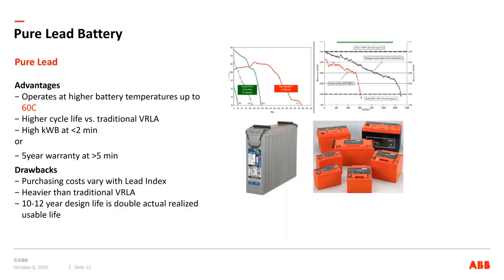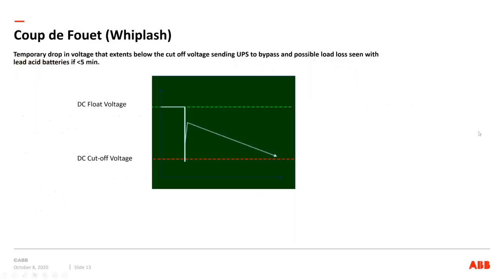The one benefit, and it'll tie into, actually we might as well go to the next slide, slide 13, with a fancy French word, coup de fouet, which is something that some data centers, some facility managers have learned the hard way. In a lead acid battery, it is chemistry. So when the UPS suddenly needs power, it's a load step on the battery, and the chemistry needs to wake up before the battery really can start to perform and supply power to the UPS. So it's also known as whiplash.